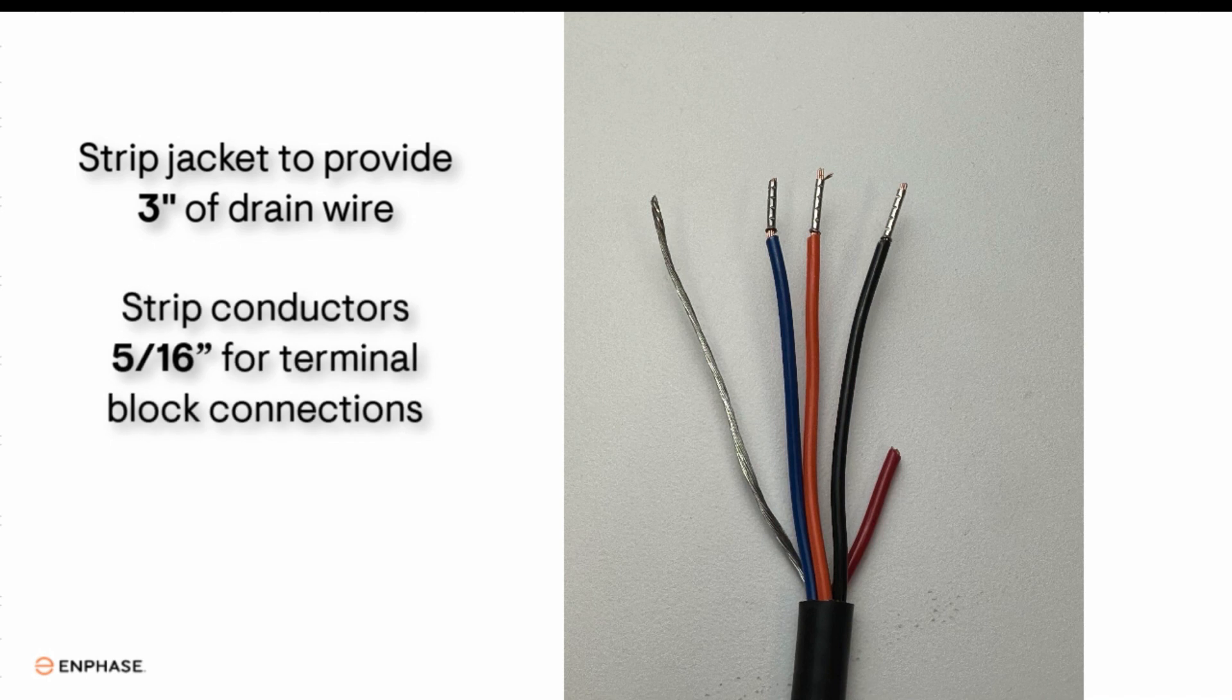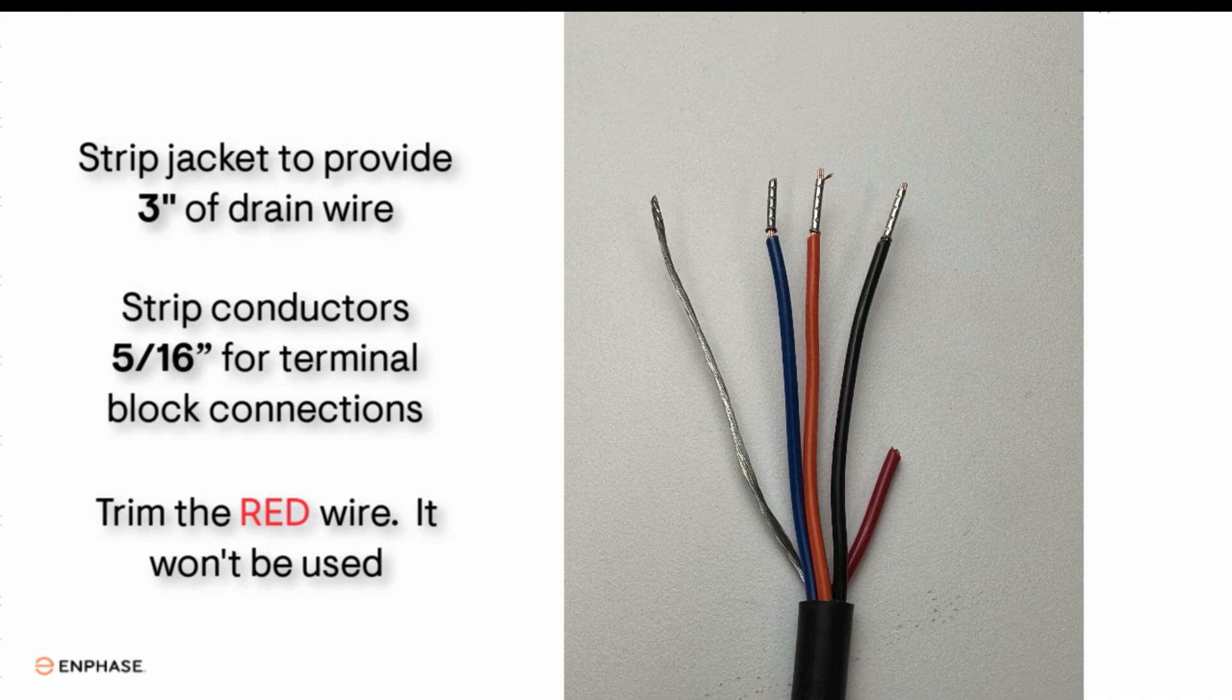Strip the control cable insulation at both ends. You'll need about three inches of drain wire. Strip back the blue, orange and black wires by 5/16th of an inch and trim the red wire down. You won't need it.